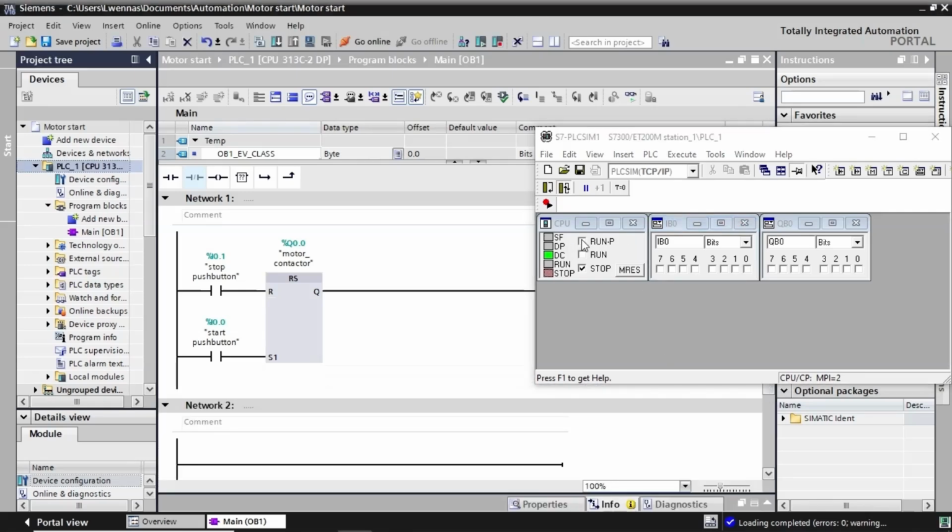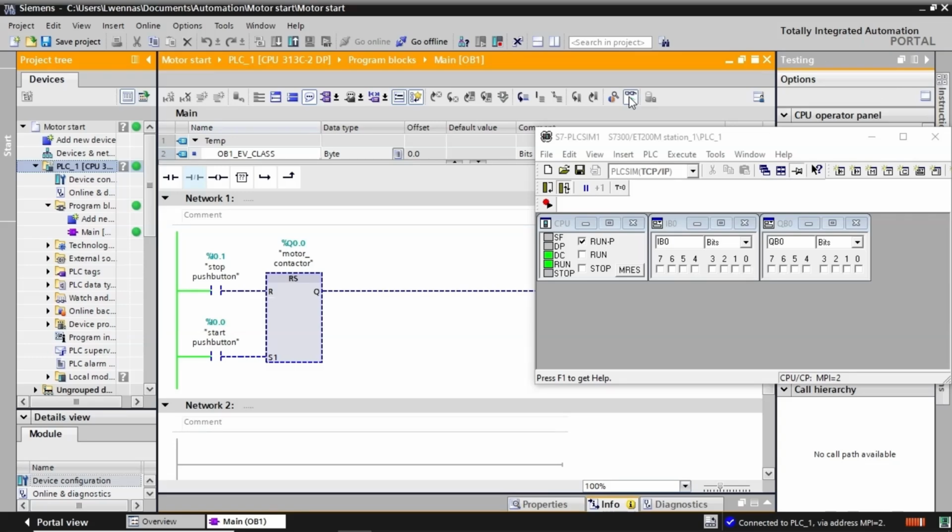Back on PLC Sim, we relaunch the simulation. We proceed similarly as with the SR flip-flop. We click on the set and release, the output turns on. To deactivate it, we click on the reset. Now we click on the set and maintain the signal. As we see, even if we click on the reset, the output will not deactivate, unlike the SR when the set is still pressed. This is the only difference between the two.